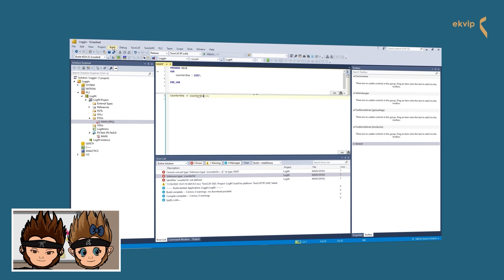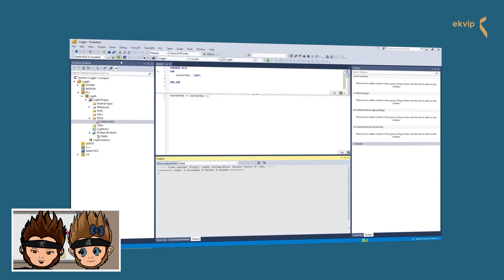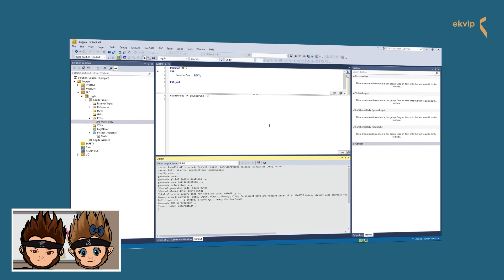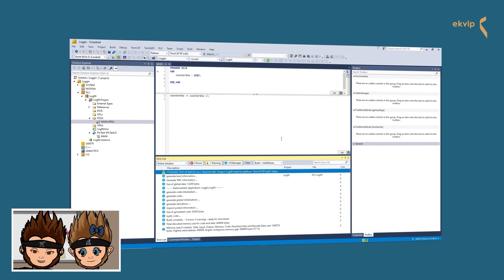It also makes sense to clean the solution before the build. If you clean the solution before building, all unnecessary temporary files will be deleted — the local compilation information for the currently active projects is deleted and the command updates the language model of all objects. If you never clean your solution, the project can become really huge over time, and that means the folder for the PLC as well. There is another command: the Rebuild Solution command, which is essentially one command for cleaning and then building the solution.